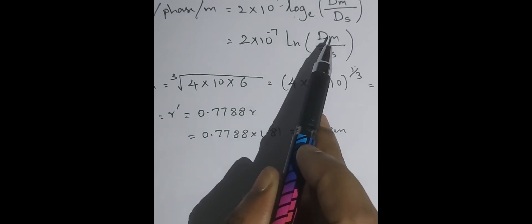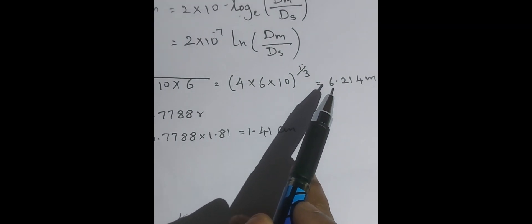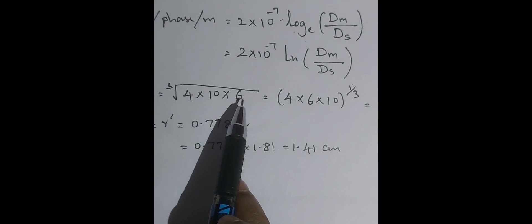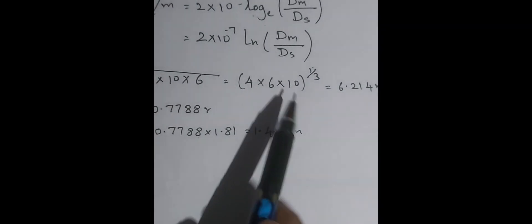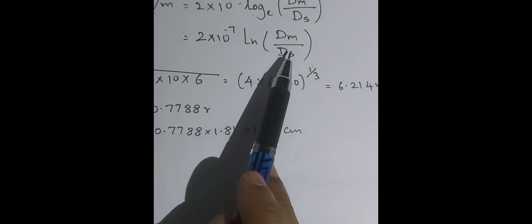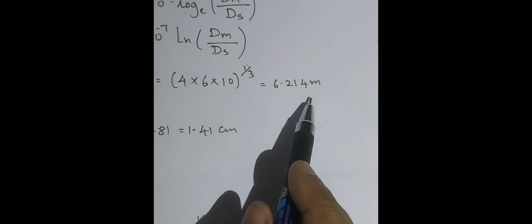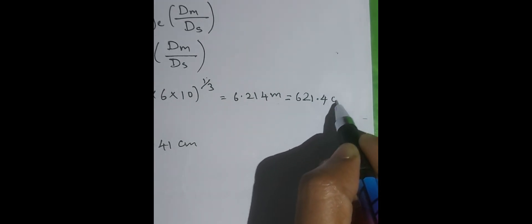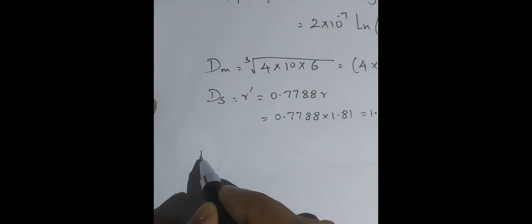Now we substitute into the formula: L = 2 × 10⁻⁷ × ln(dm / ds). Notice dm is in meters (6.214 m) and ds is in centimeters (1.41 cm). We must use the same units. It is better to convert dm from meters to centimeters by multiplying by 100, giving 621.4 centimeters. Now both dm and ds are in centimeters.